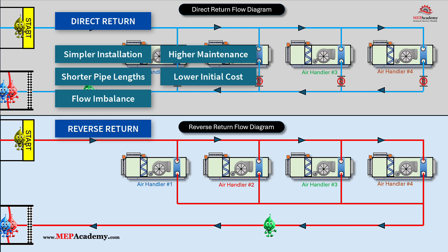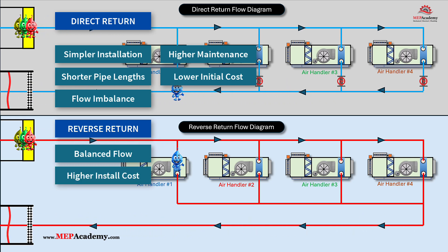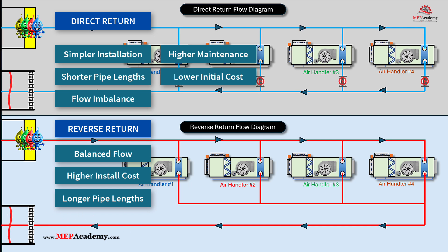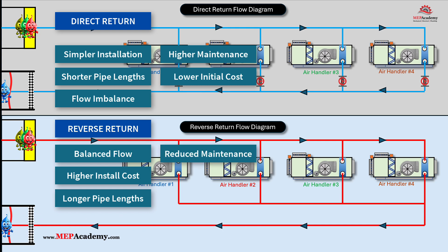Reverse return piping: naturally balanced flow — the design ensures equal pipe lengths to and from each terminal unit, aiding in consistent flow and easier balancing. However, more piping material and complex routing increase initial costs and installation time. Longer total pipe length requires additional piping to loop back the return path, impacting space and cost. Reduced maintenance — less need for frequent adjustments due to the self-balancing nature of the system. These points highlight the trade-offs between the simpler, cost-effective direct return and the more balanced but costlier reverse return systems.